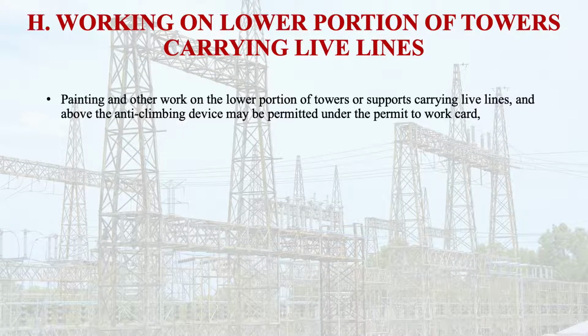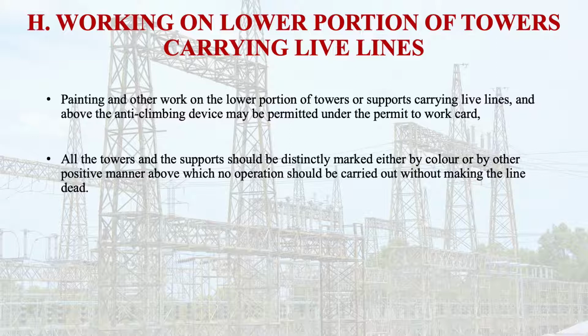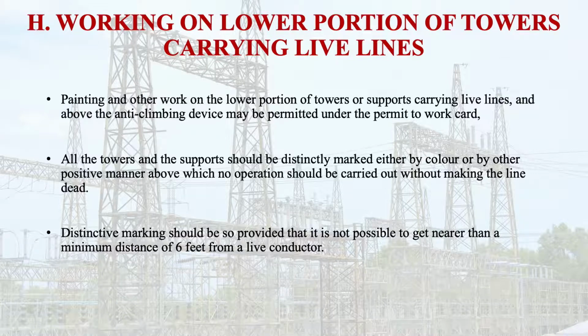So for this purpose, all the towers and supports should be distinctly marked either by color or by other positive manner, above which no operation should be carried out without making the line dead. Only up to that mark, and above that mark no operation should be carried out without making line dead. So distinctive marking should be so provided that it is not possible to get nearer than a minimum distance of 6 feet from a live conductor.